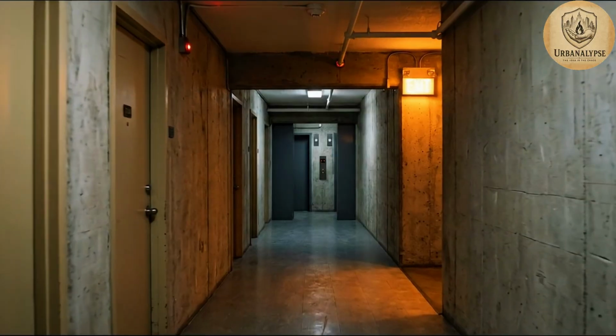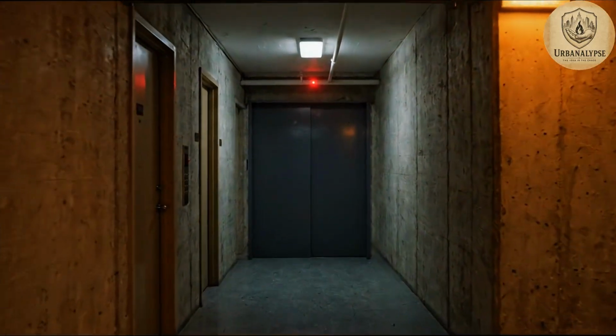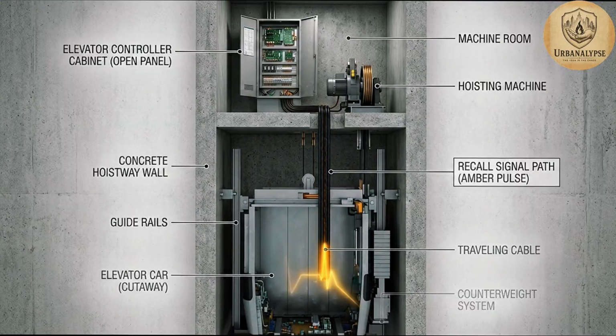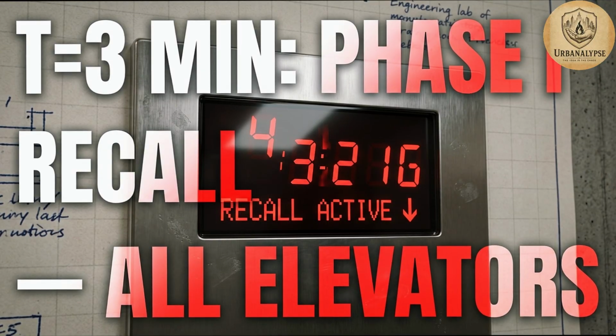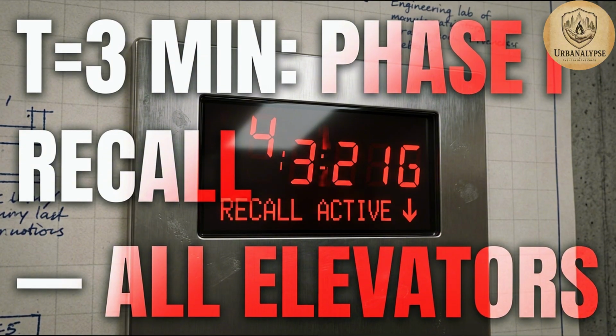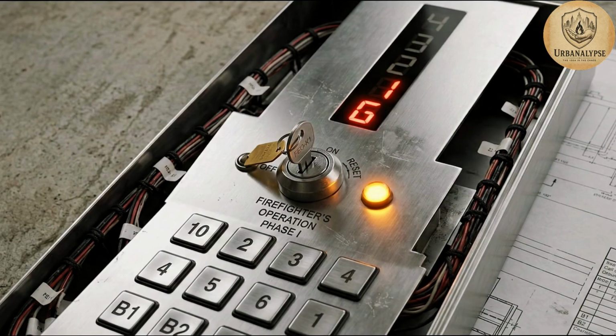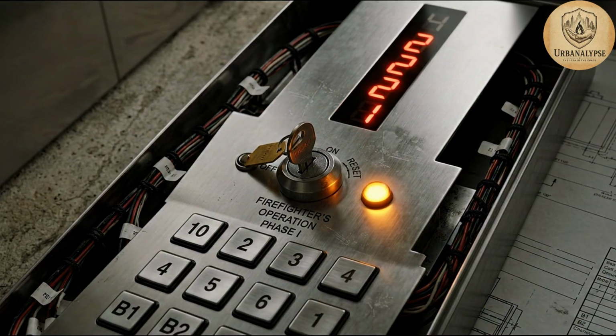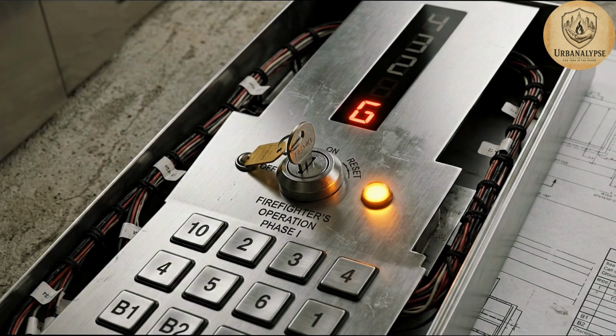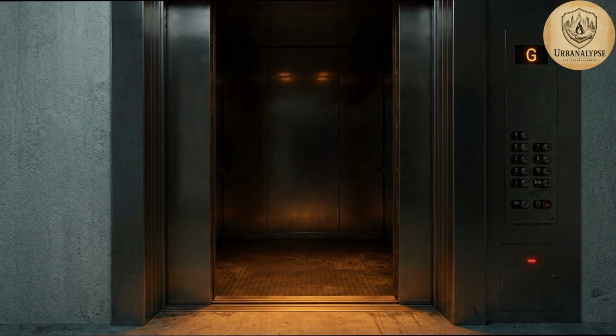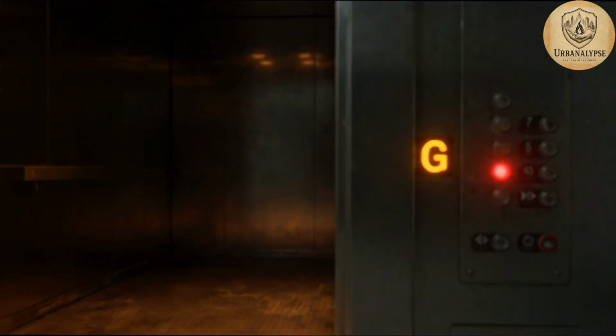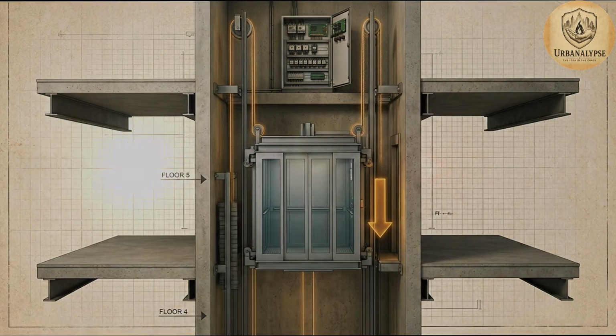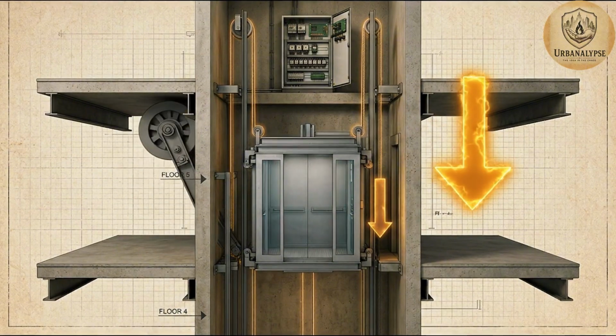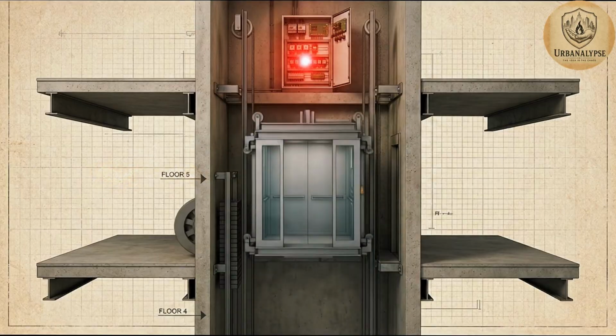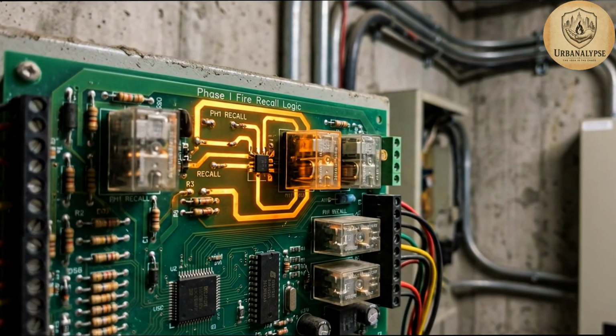The branch exists for egress, and 4 floors below your unit, the elevator system is already executing a separate, unrelated protocol of its own. Between T3 minutes and T4 minutes, the elevator controller initiates Phase 1 emergency recall under ANSI ASME A17.1, sending every car in the bank directly to the ground floor, holding the doors open, and taking the entire bank offline until stable power, grid or generator, is confirmed by onboard control logic. If a car happens to be between floors when the recall signal fires, it proceeds to the nearest floor in the direction of travel before opening, a fail-safe written directly into the controller's firmware, not left to chance.